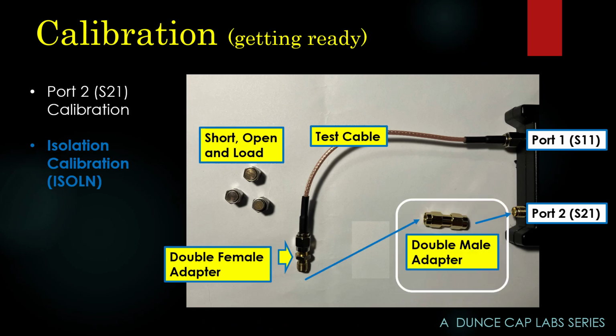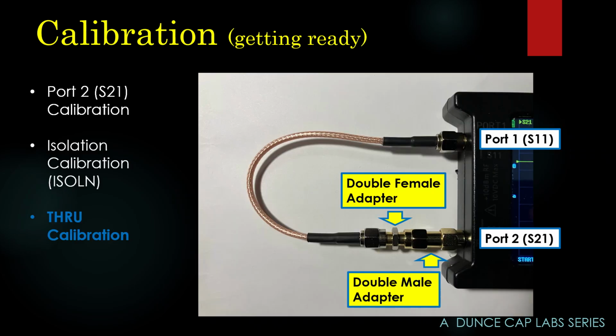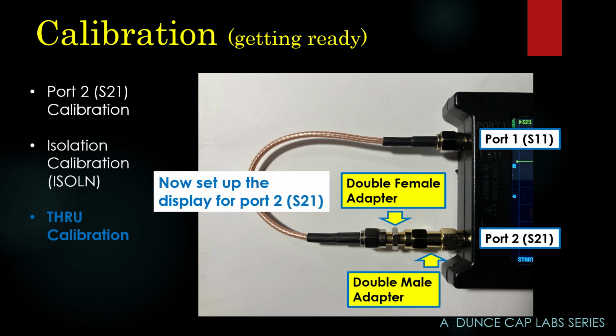Once you get port 1 done, you're going to take the load off the double female adapter and move it to port 2 and then hit the isolation button. Then you're going to take the dummy load off and you're going to use the double male adapter to form a loop and do the through calibration with the through button. And that's it. I'll walk you through this in a minute. One last item. You're going to have to set up the display for port 2.